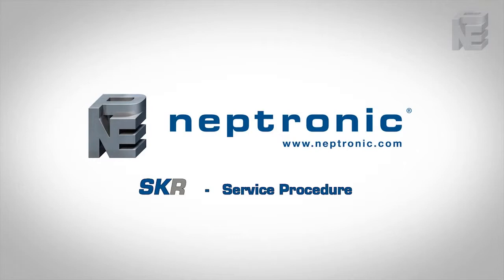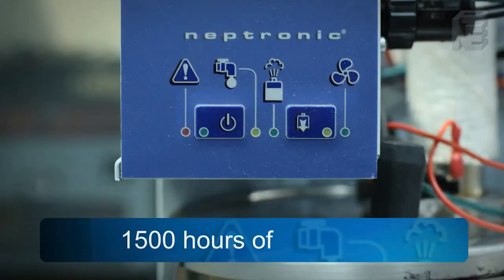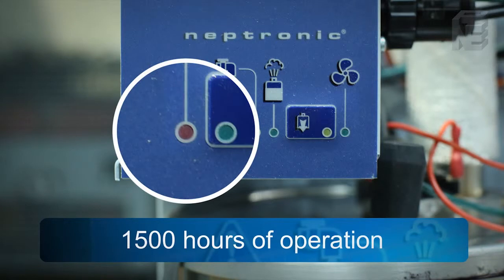SKR service procedure. When the humidifier reaches 1,500 hours of operation, the red LED alarm indicator will blink on-off continually, letting you be aware that the unit should be serviced soon.